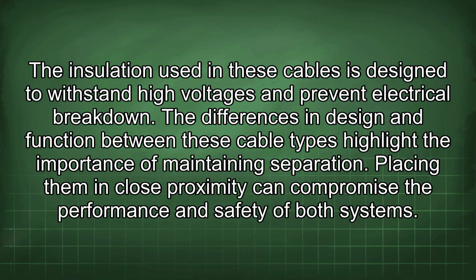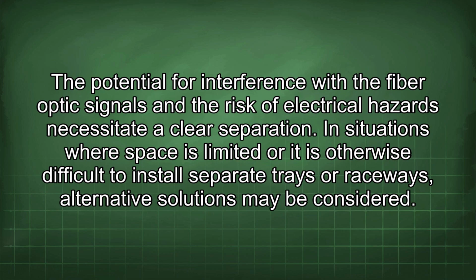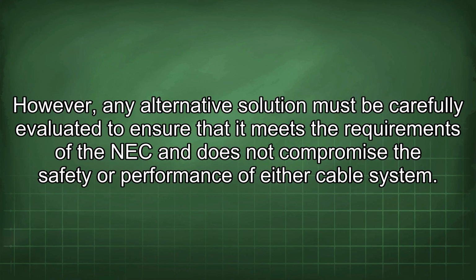The differences in design and function between these cable types highlight the importance of maintaining separation. Placing them in close proximity can compromise the performance and safety of both systems. The potential for interference with the fiber optic signals and the risk of electrical hazards necessitate a clear separation. In situations where space is limited or it is otherwise difficult to install separate trays or raceways, alternative solutions may be considered. However, any alternative solution must be carefully evaluated to ensure that it meets the requirements of the NEC and does not compromise the safety or performance of either cable system.